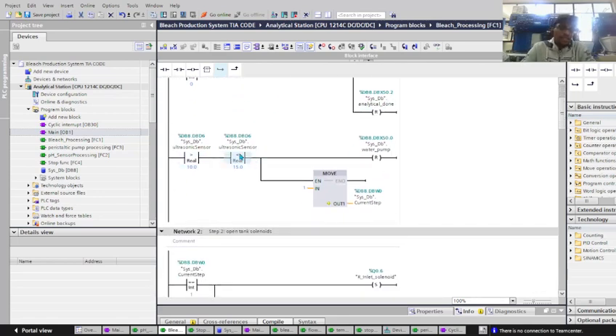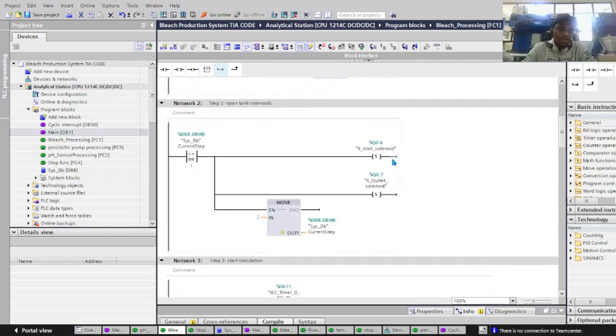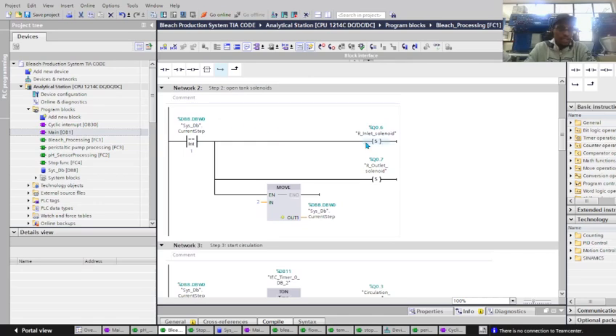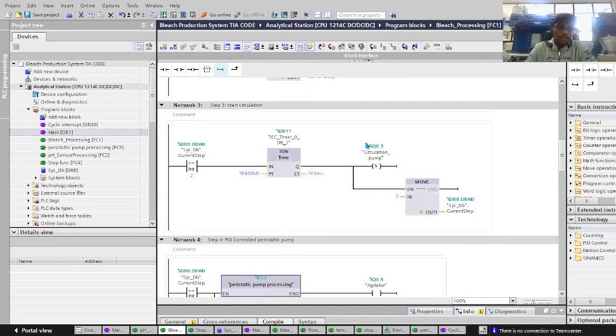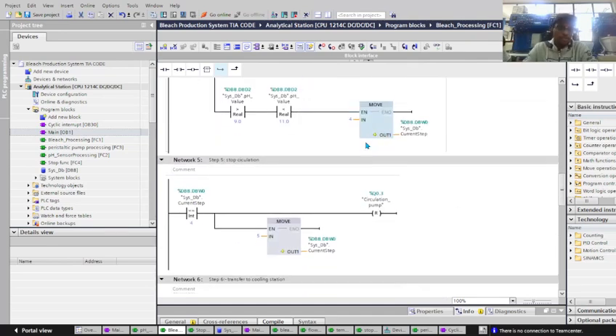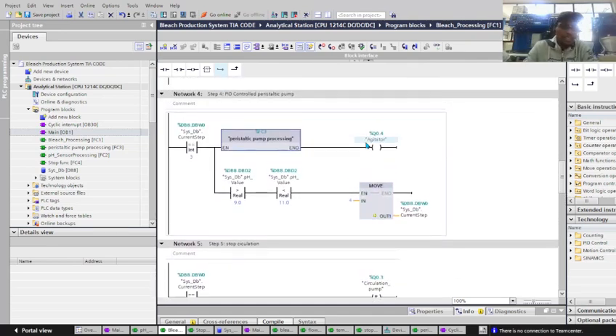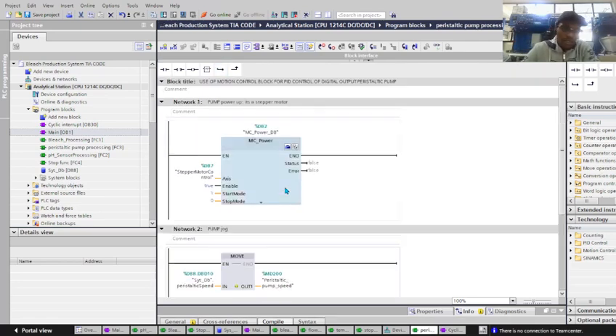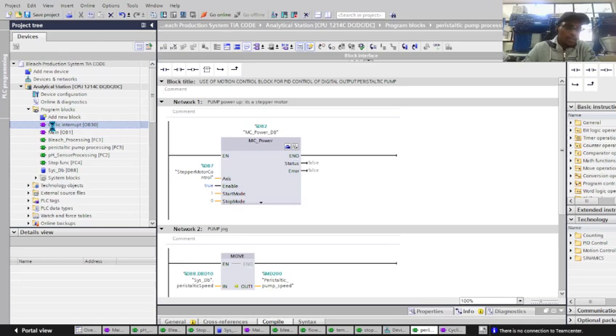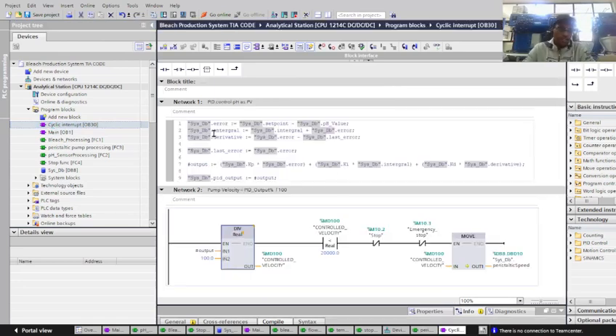Once it has reached the right value, it resets the water pump, and then we open the inlet and outlet solenoids for the process tank, and then we start the circulation pump, and then start the peristaltic pump and the agitator. The peristaltic pump we are using to pump the concentrated calcium hypochlorite into the process tank, and we are controlling its speed using a PID controller that we have made.